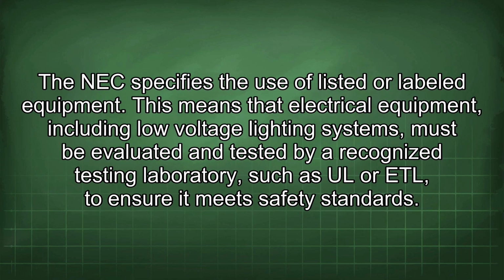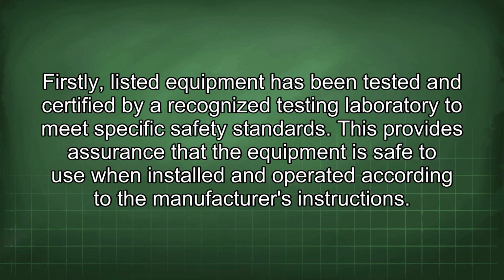The NEC specifies the use of listed or labeled equipment. This means that electrical equipment, including low-voltage lighting systems, must be evaluated and tested by a recognized testing laboratory such as UL or ETL to ensure it meets safety standards. Firstly, listed equipment has been tested and certified by a recognized testing laboratory to meet specific safety standards. This provides assurance that the equipment is safe to use when installed and operated according to the manufacturer's instructions.